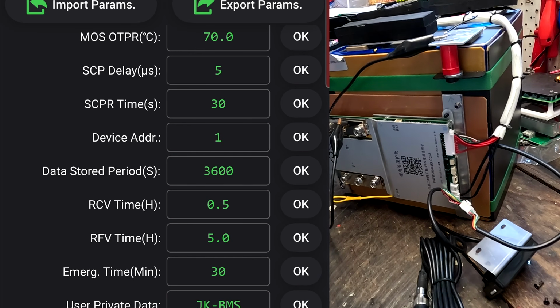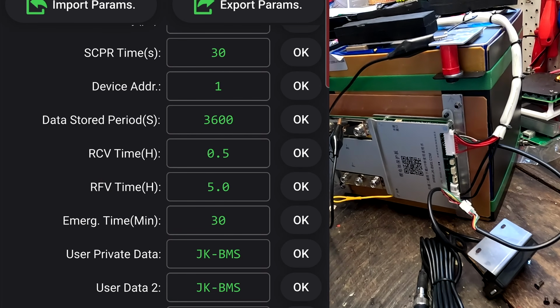Device address, RCV timer for half an hour. That should be enough to fully balance this battery. The RCV timer is only interesting for the reset of the BMS to 100% state of charge. So it needs to sit on 3.45 volts for half an hour. And then it resets to 100%.